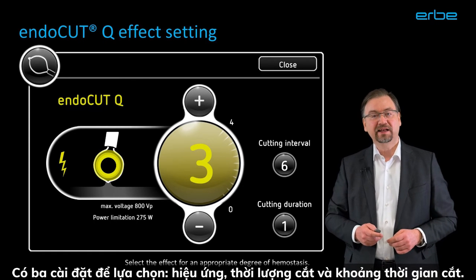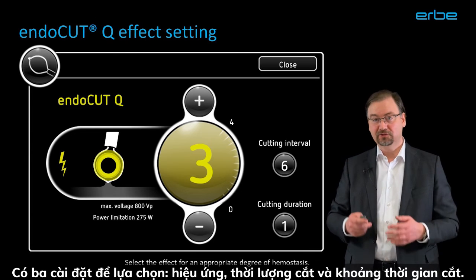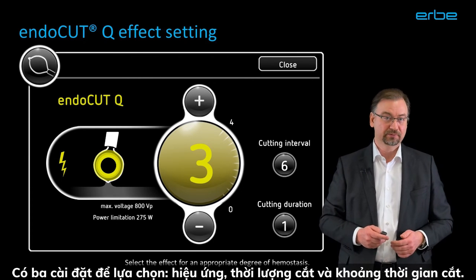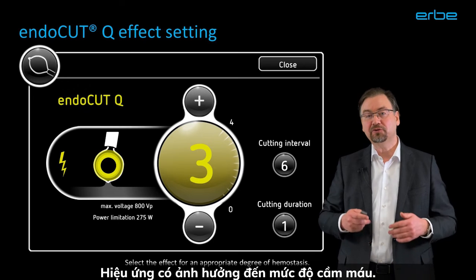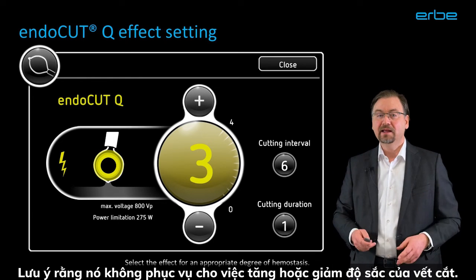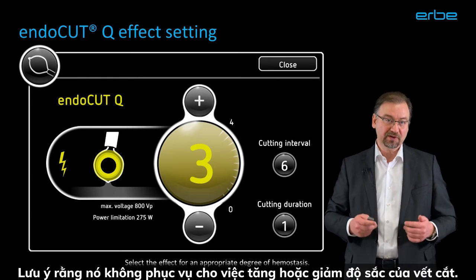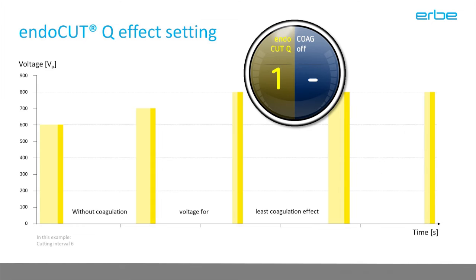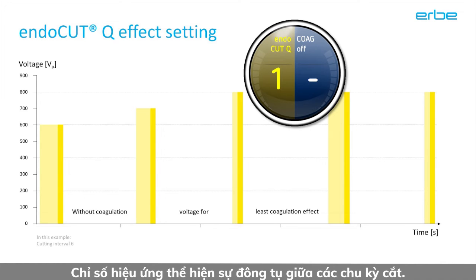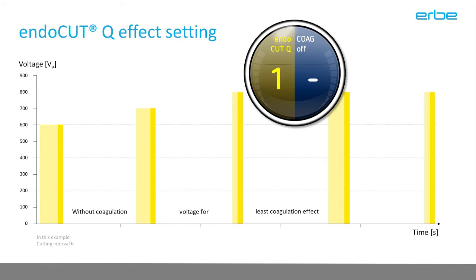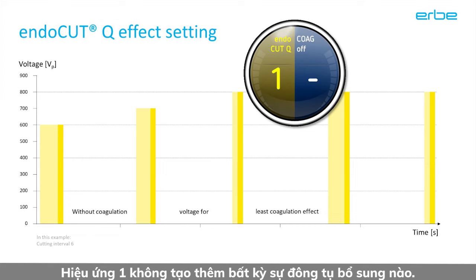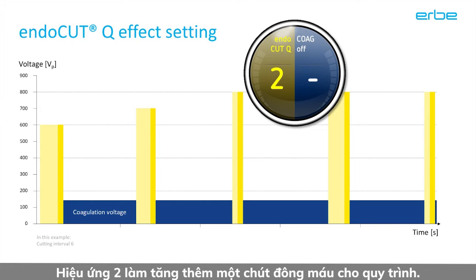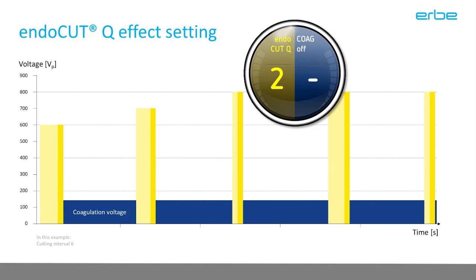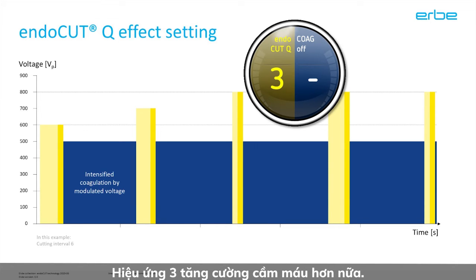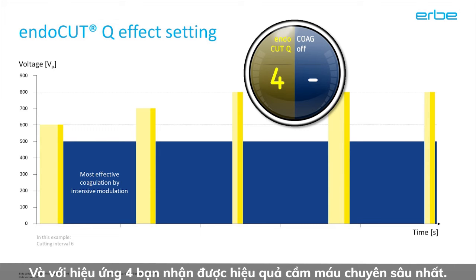There are 3 settings to select from: the effect, the cutting duration, and the cutting interval. The effect has an impact on the degree of hemostasis. Note that it does not serve to increase or decrease the cutting sharpness. The effect number is about the coagulation in between the cutting cycles. Effect 1 does not add any additional coagulation. Effect 2 adds a little more coagulation to the procedure. Effect 3 intensifies the hemostasis even more, and with effect 4, you receive the most intensive hemostatic effect.